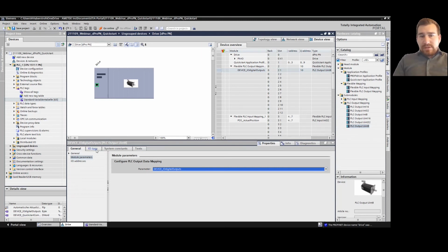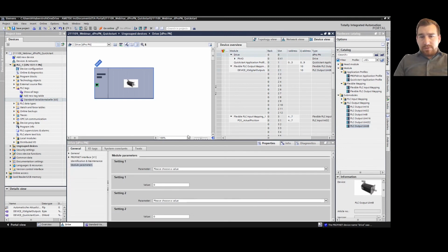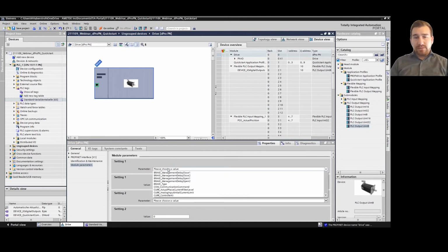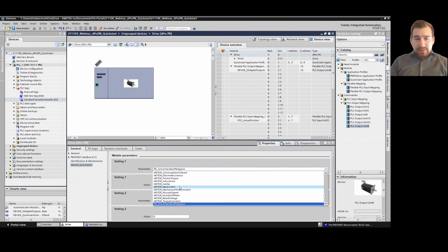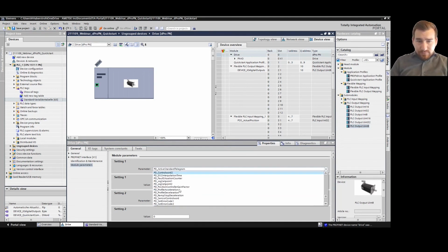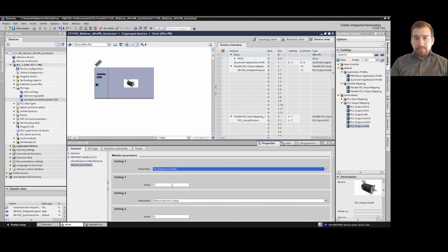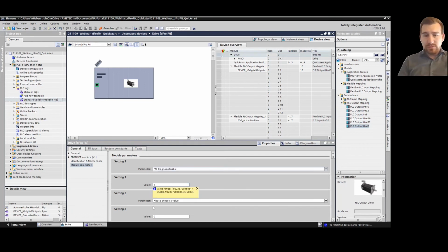The next functionality we have, if we go into the properties of the motor, we have the module parameters. And here we can set up the startup parameters, up to 64 parameters, which are always written when the motor is connected or when the connection is assembled between motor and PLC. And I will recommend to set up here the Profinet diagnostic. It's down here. If you write here a 1 into it, we will see it later.